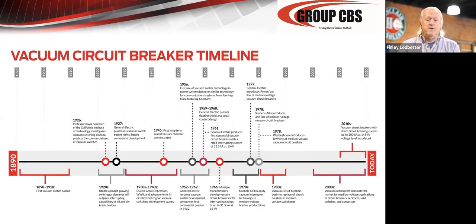This particular timeline chart kind of shows when the breakers were developed, when they came into use, and when they got real popular. If you look at this, in the 20s, in the 30s, in the 40s, there was a tremendous amount of design work being done around how do we increase the interrupting rating of a vacuum breaker to get it to be able to do the job. It was very easy for them to build a vacuum interrupter that would interrupt about 10 kA, about 10,000 amps of AC current. But to get past that point, it took some metallurgy and it took some physics, because they could not get past it.